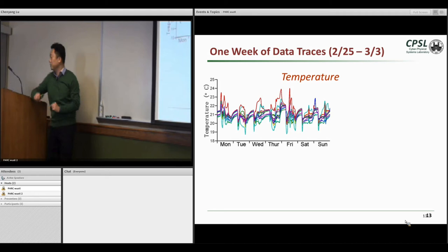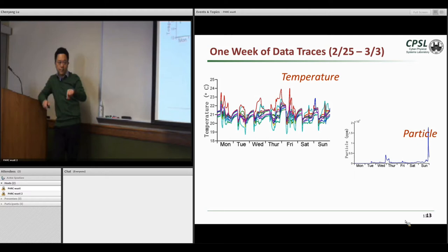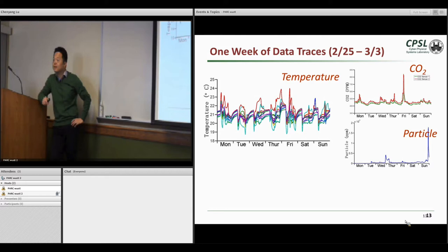This is particle counter data—we see the air quality of the rooms does change depending on the events and HVAC operations going on in the auditorium. CO2 is usually used as a proxy for occupancy, and you can see it fluctuate depending on the events held in the auditorium.